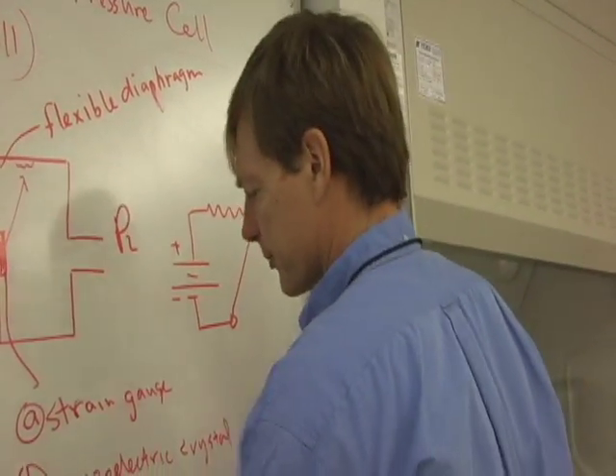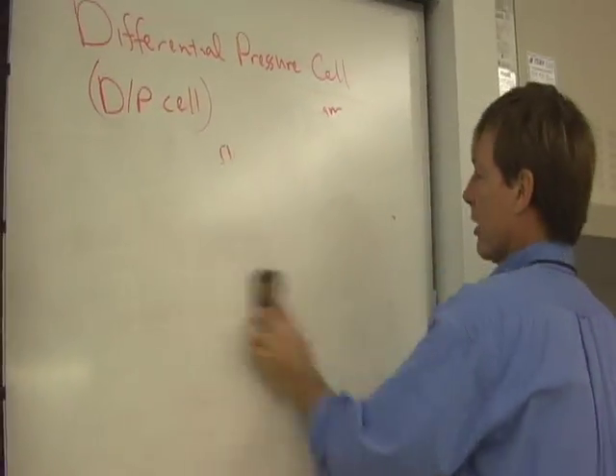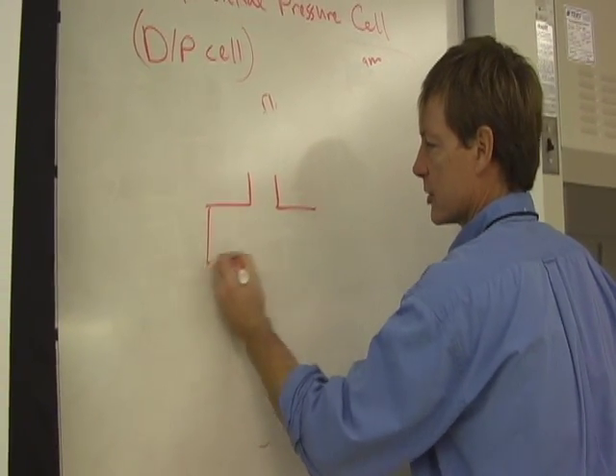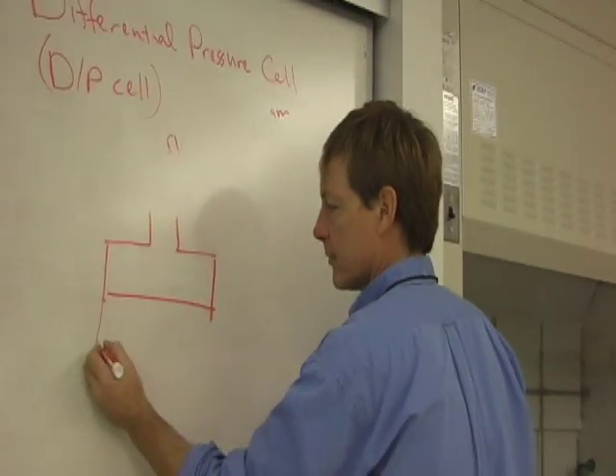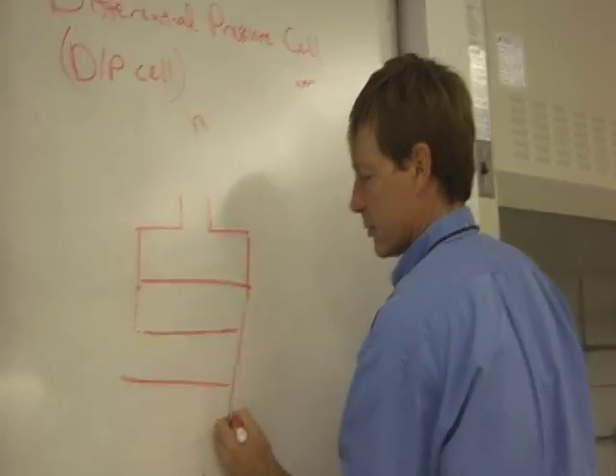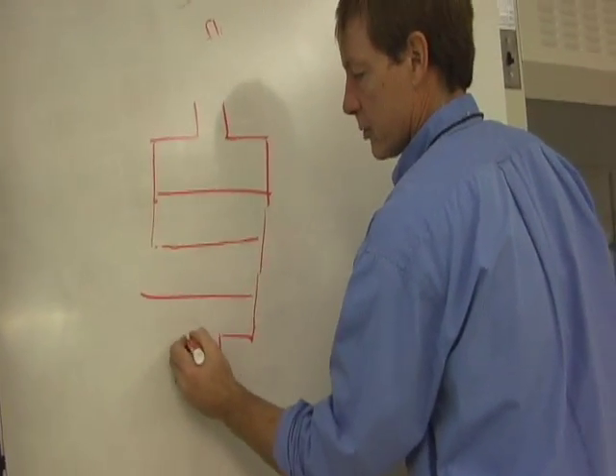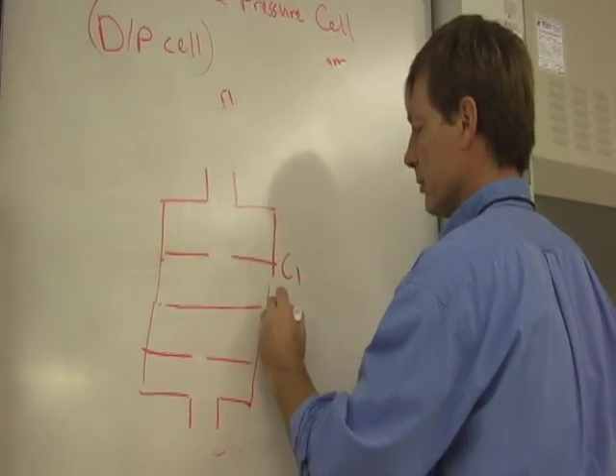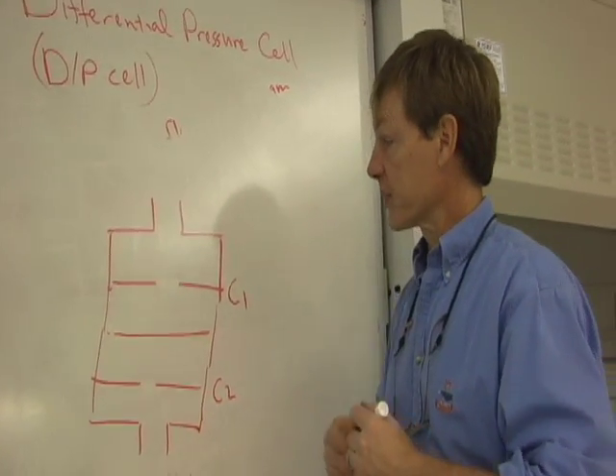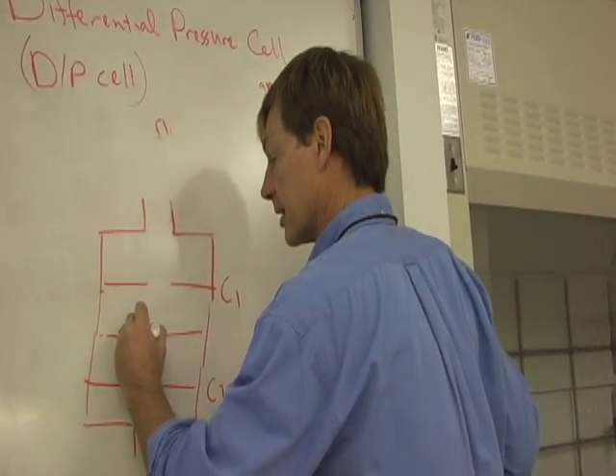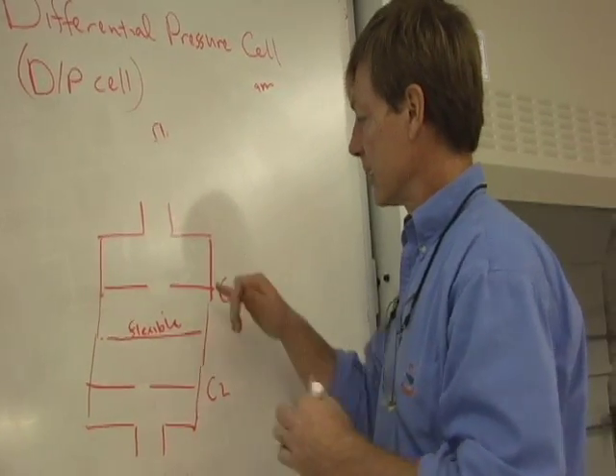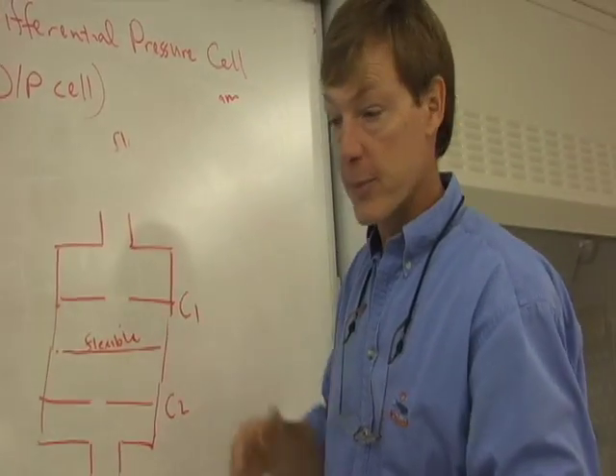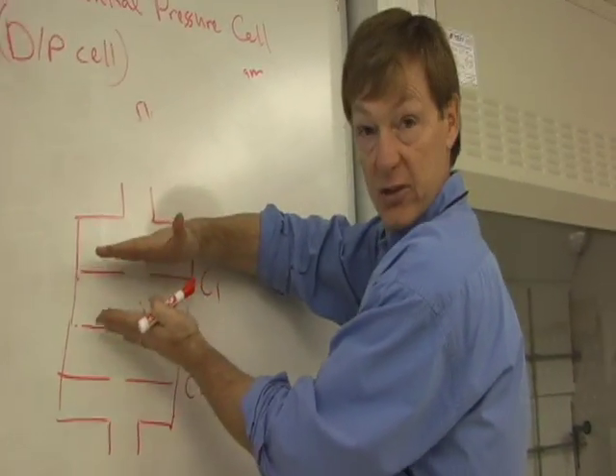One more option on these, DP cell. I can also take it and run it. I'm just changing the shape and the orientation, that's no big deal. Put a hole there and a hole there. C1, C2. This is capacitance-driven. What happens is this is a conducting plate and it's flexible. And these are two conducting plates too. So these are capacitors. A capacitance, one of the properties of capacitance is, well, one of the things that controls it is the distance between the plates.